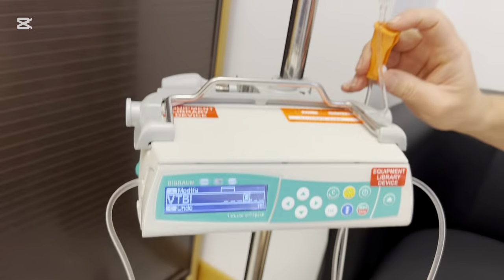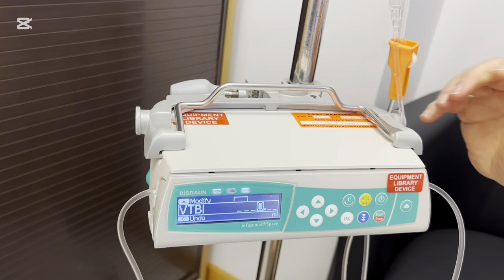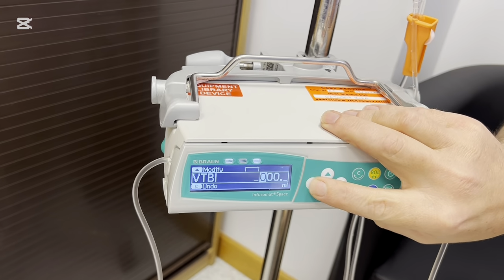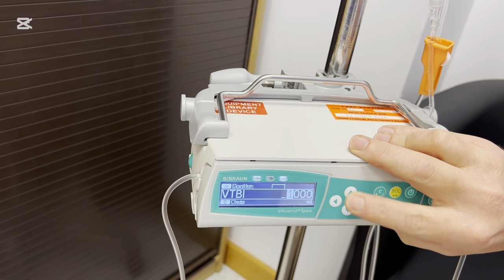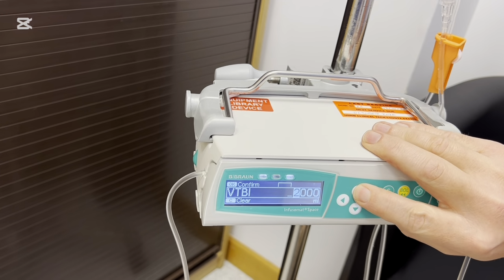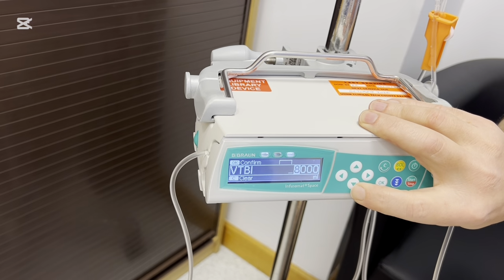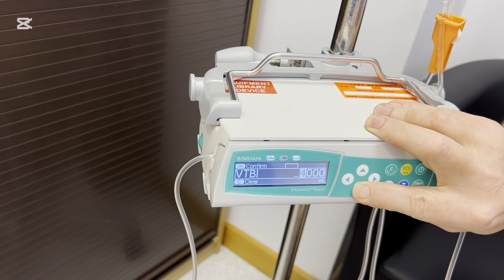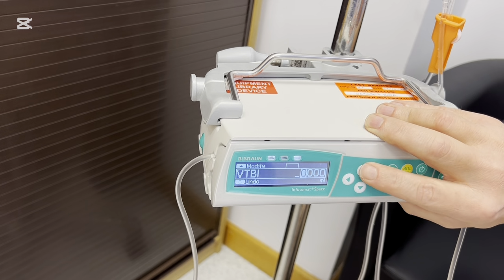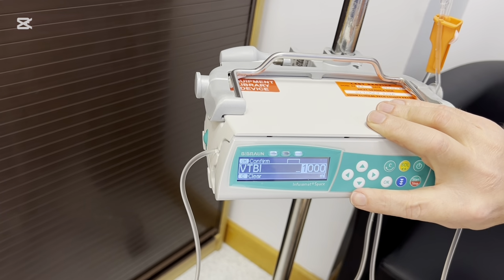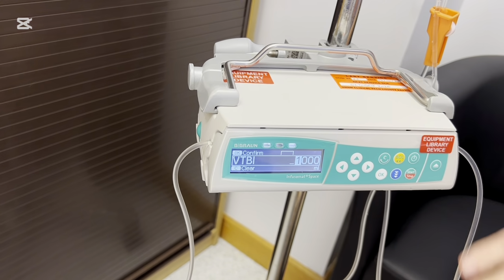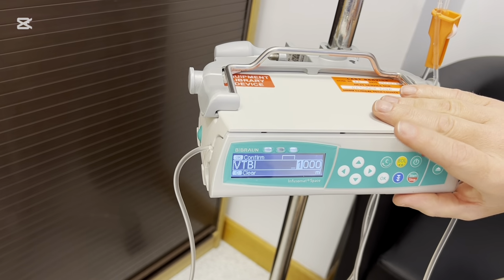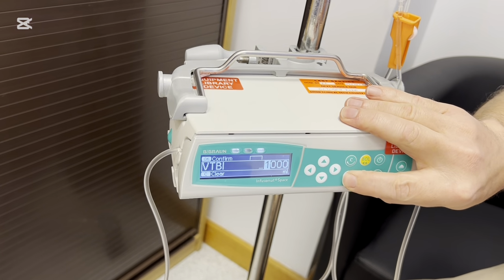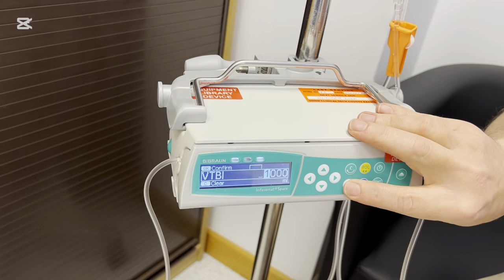So it now says we can open the roller clamp. We now can select the volume to be infused. So we'll select 1000. The highest volume we can select, maximum we're going to select routinely, is going to be a litre. I can see that for people having TPN, you might possibly want to select 3+ litres over a day. But for most fluid infusions that we'll be responsible for, it's going to be no more than a litre bag at a time. So, OK to confirm.